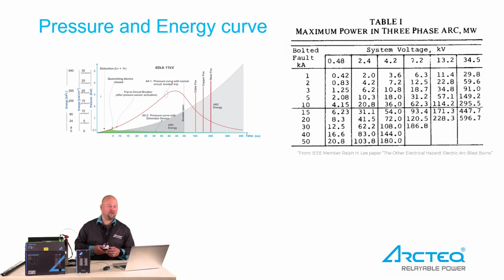And top left there is another curve. This is from 11 kV. We are talking more about low voltage today, but the pressure curve, the current curve and the timing curve are pretty much similar. The difference is more that when you have higher voltage, the arc flash can ignite more easily, but the strong current is the thing which is burning the electrode, burning the ionized air and copper. So, pressure and energy curve, just information and knowledge.